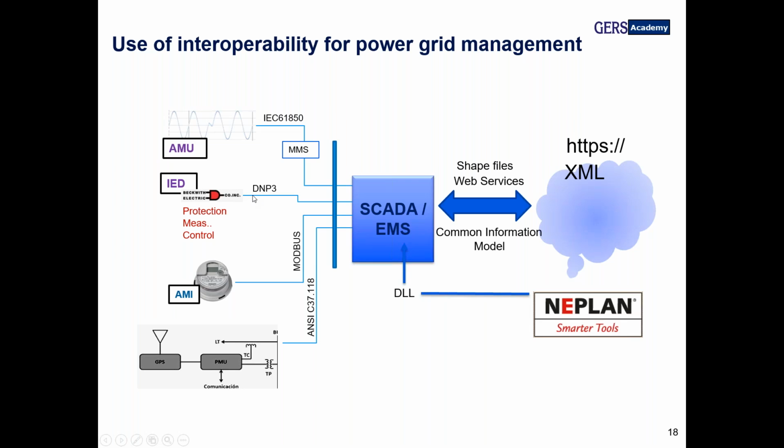The IEDs can also approach another communication protocol, and to date, we can also check how we could use the new standard. That standard has been increasing in applications, the 61850, for communication between IEDs and between the IEDs and the substation, when we are increasing the approach using reports. And as we can see here, all the information is being centralized on the SCADA system.